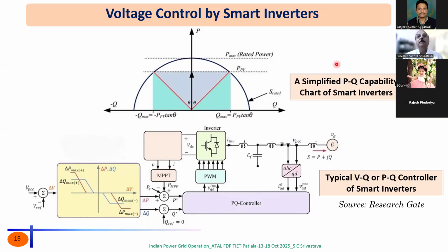In fact, one of the blackouts that recently happened in April this year is the Iberian one, everybody is talking about Spain and Portugal. There, one of the main reasons was that the lot of renewables they had had no voltage control mechanism, so overvoltage was seen. Because of that, generators tripped and multiple tripping took place.